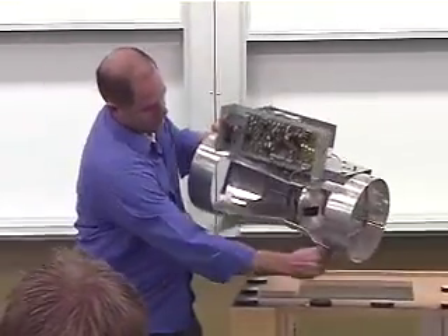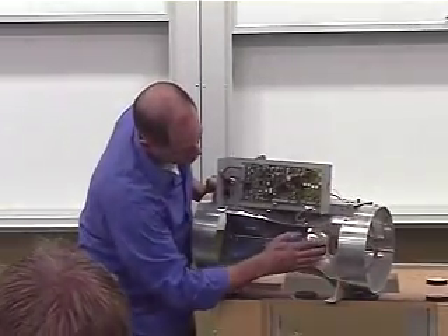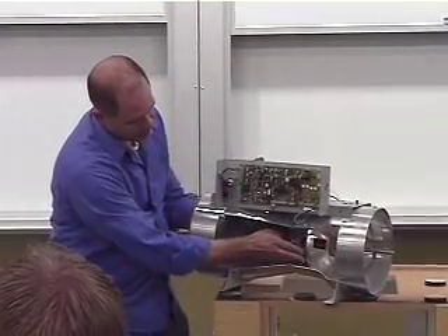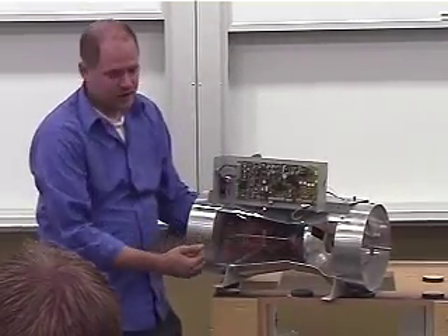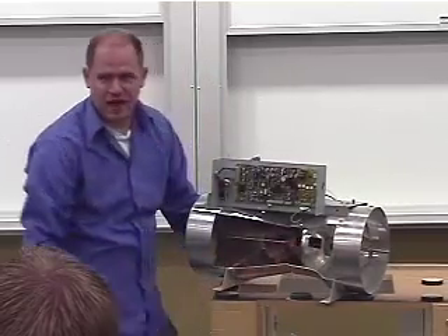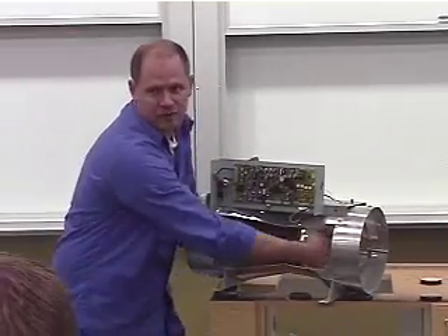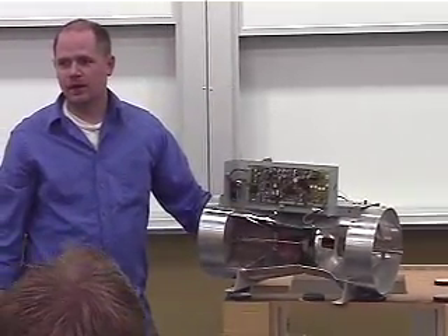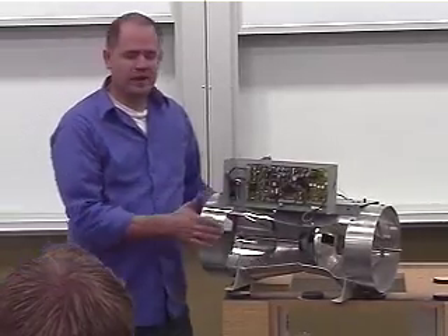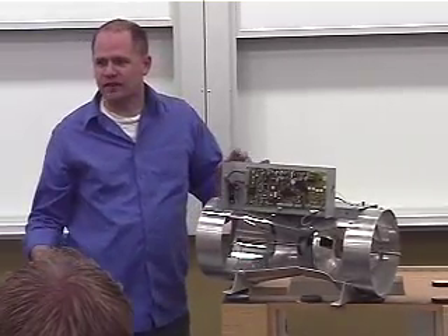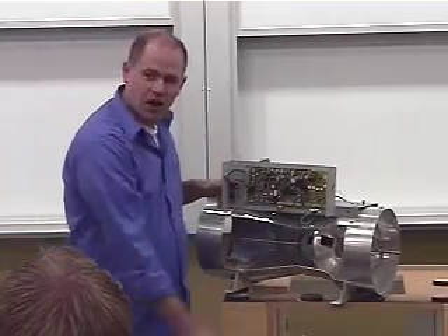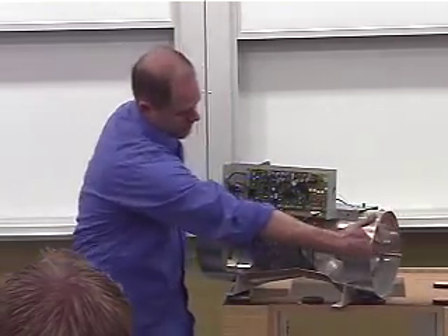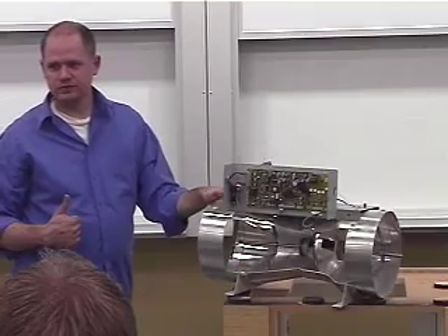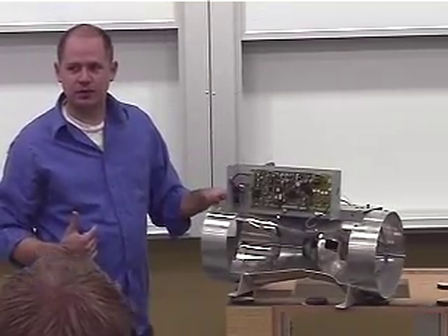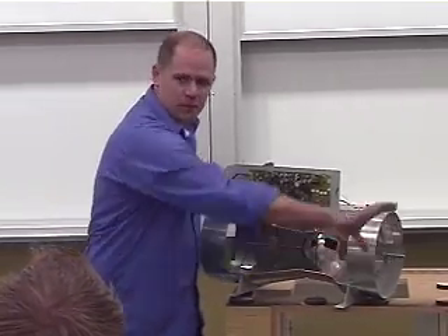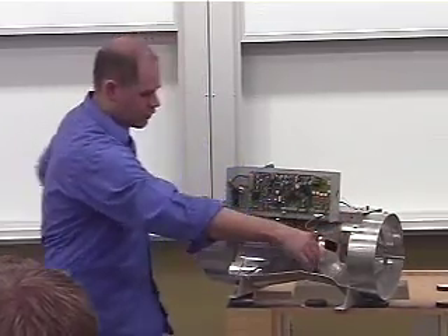Obviously, this cone has a more rounded side and then this more flat side that kind of comes back. So the airflow is coming this way on this valve. It has to hit the rounded top of the cone first. Typically they throw an arrow on the outside of the valve so you can see which way that's going. So if you're in an exhaust scenario, the room side is over here and airflow is coming across there. If you're in a supply scenario, this side of the valve should be pointed up at the air handler, and your room side is over here.